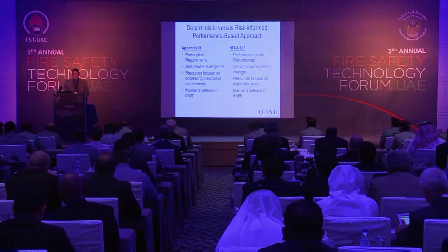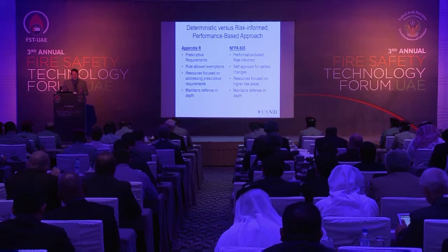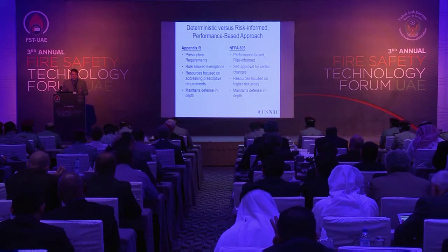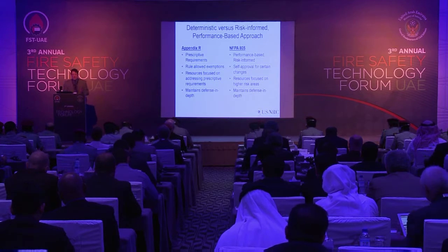By using this approach, resources can be focused on higher risk areas. However, implementation of this method maintains a focus on defense in depth, which has proven to be a sound regulatory approach in the U.S. So just as I described before, you still have the layers of protection, the defense in depth, the emphasis on detection, the emphasis on suppression, the emphasis on fire barriers and separation, but you're doing it in a smarter way, and you're looking at those fire areas or those areas of the plant that are really more susceptible and would result in the greatest contribution to risk.